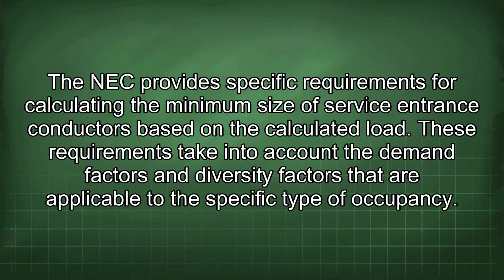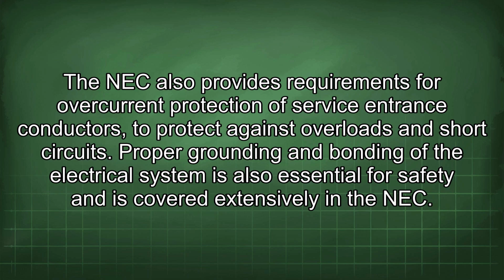These requirements take into account the demand factors and diversity factors that are applicable to the specific type of occupancy. The NEC also provides requirements for overcurrent protection of service entrance conductors to protect against overloads and short circuits. Proper grounding and bonding of the electrical system is also essential for safety and is covered extensively in the NEC.